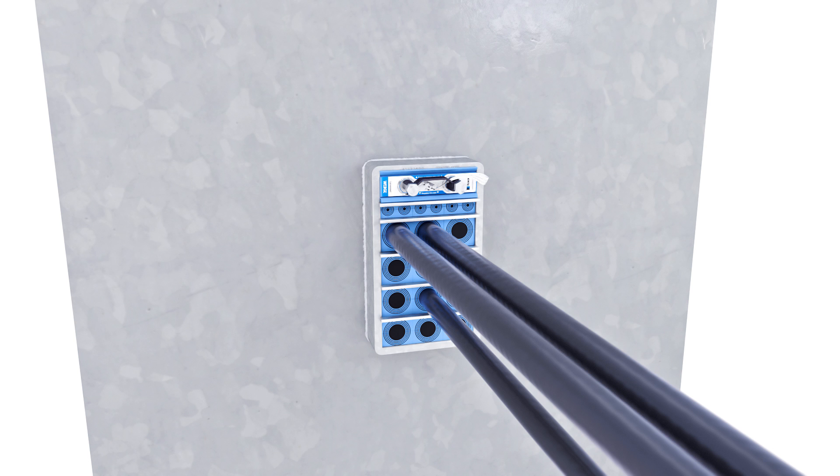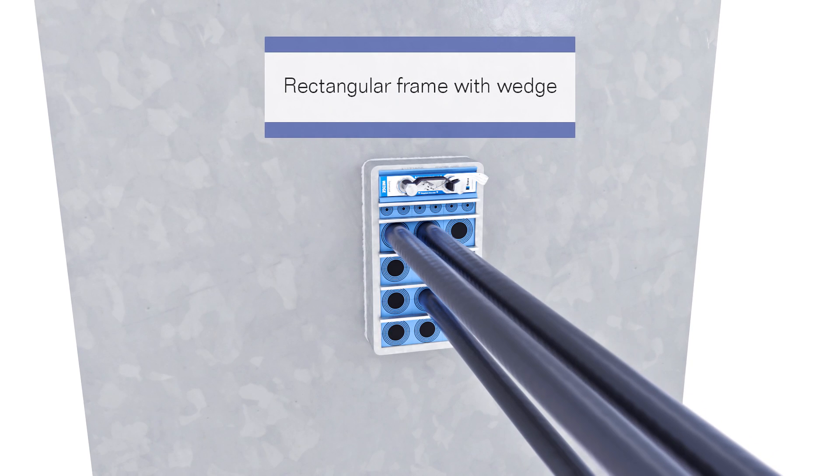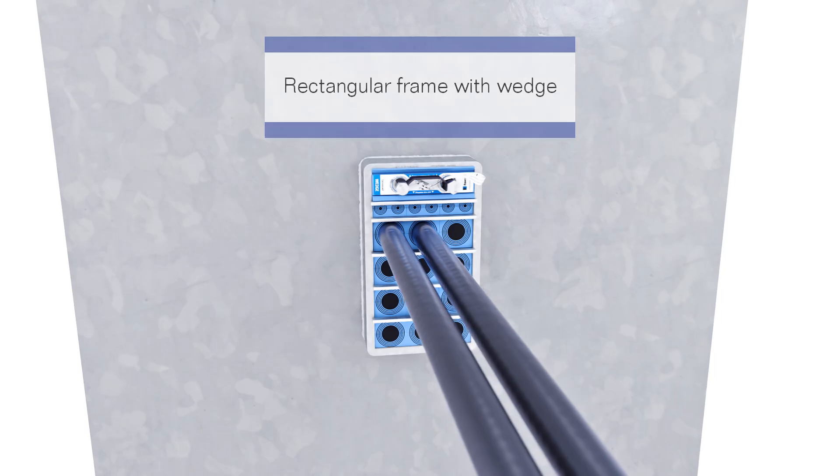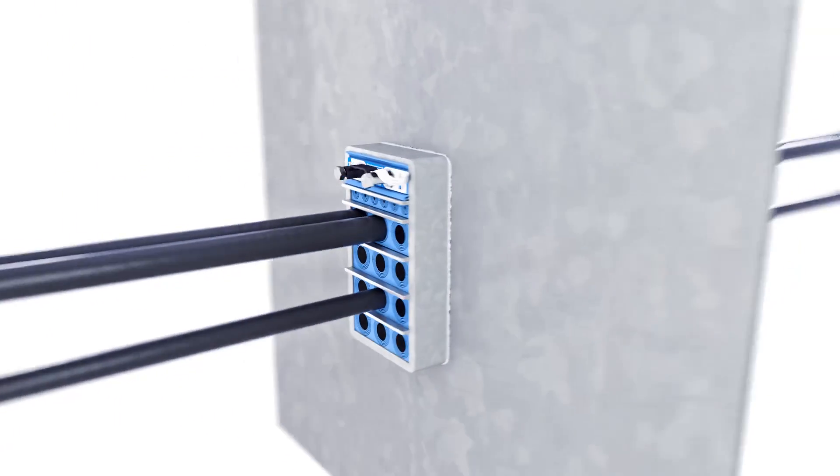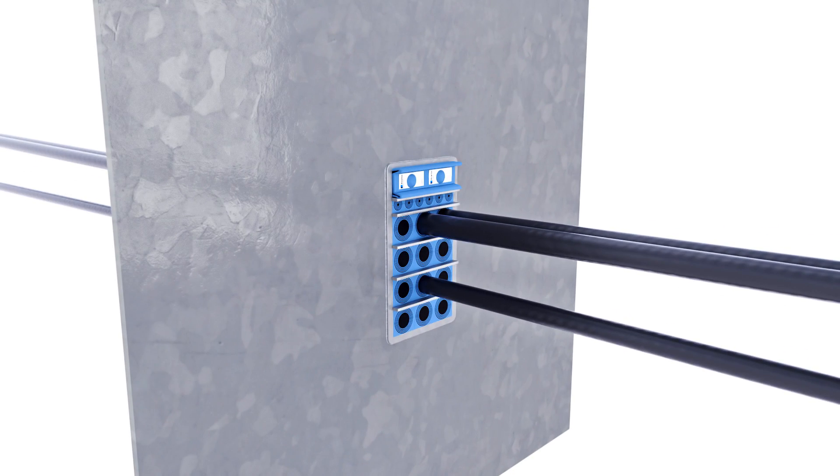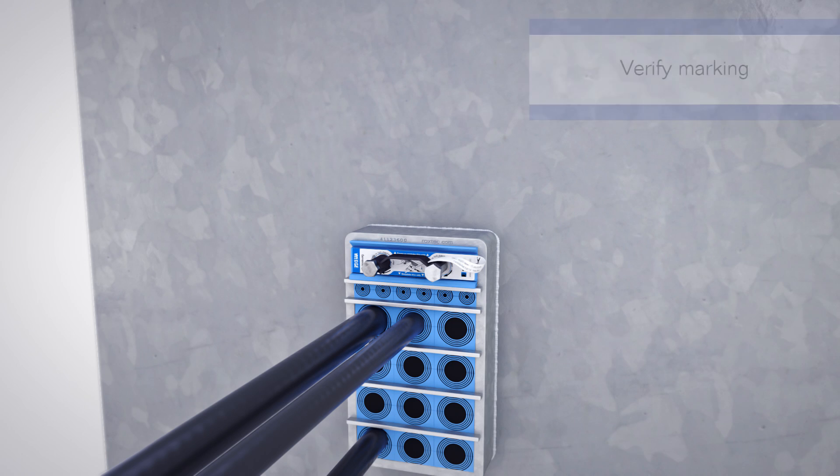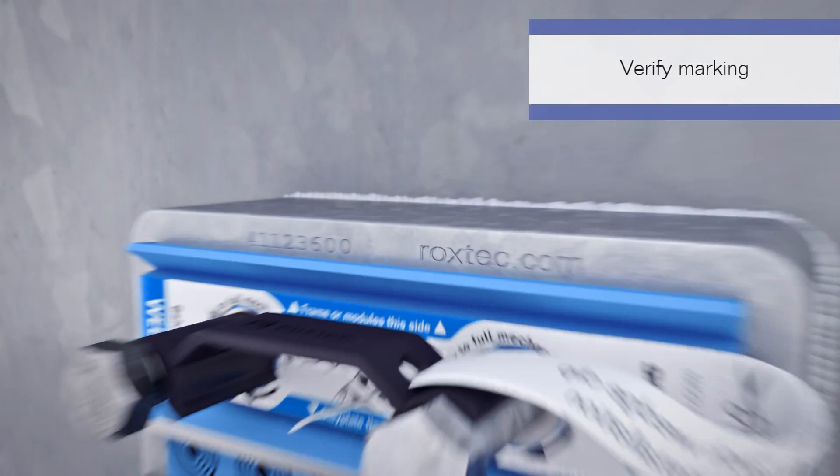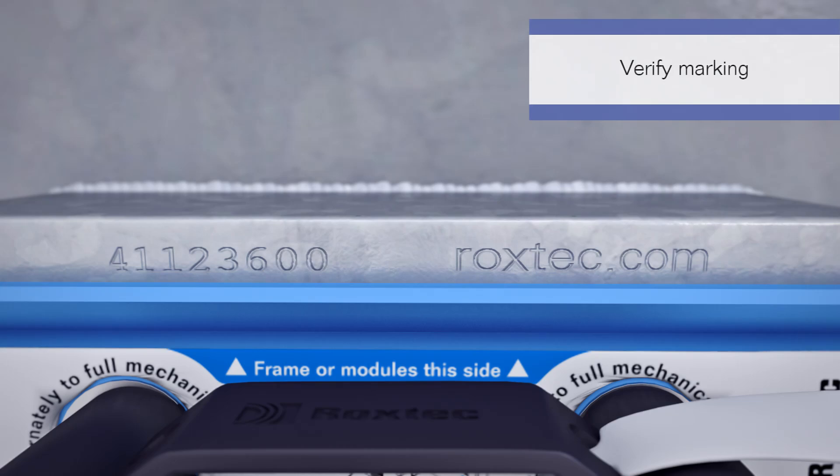Let us guide you along the way. This is how you check the installation quality for a rectangular Roxtec frame with wedge. If possible, check the transit from both sides. If possible, verify the marking to make sure that you use an original Roxtec frame.